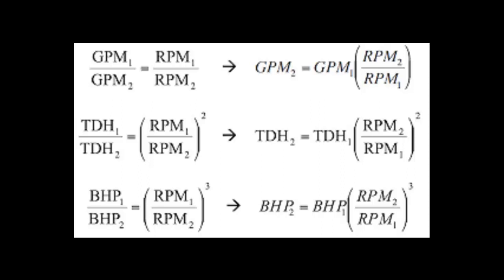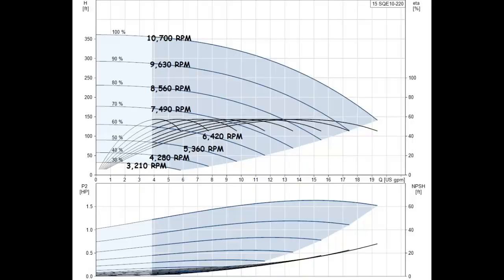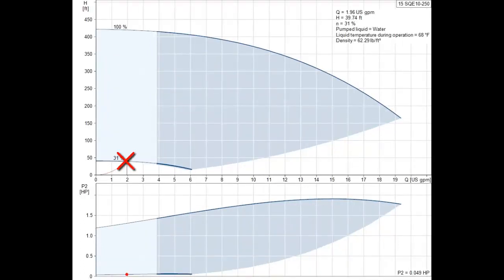Many engineers preach about the affinity law. They make a big deal about how horsepower is reduced by the cube of the speed, which shows a 50% reduction in speed will cause almost a 90% reduction in energy use. With this electronic pump curve, there are lines marked all the way down to 30% pump speed. If you place a point at 30% speed and 2 gallons per minute, it will show the horsepower will drop all the way down to 0.049 of a horsepower.